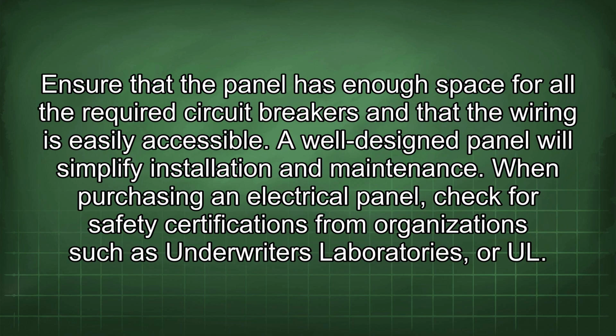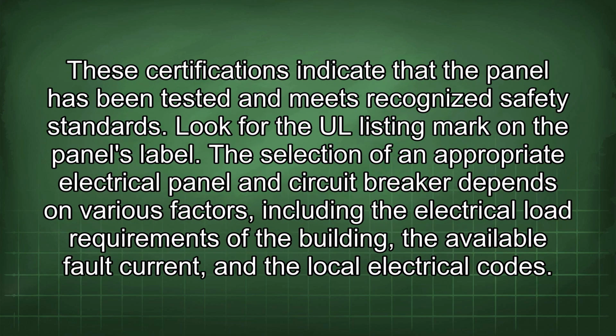Ensure that the panel has enough space for all the required circuit breakers and that the wiring is easily accessible. A well-designed panel will simplify installation and maintenance. When purchasing an electrical panel, check for safety certifications from organizations such as Underwriters Laboratories, or UL. These certifications indicate that the panel has been tested and meets recognized safety standards. Look for the UL listing mark on the panel's label.